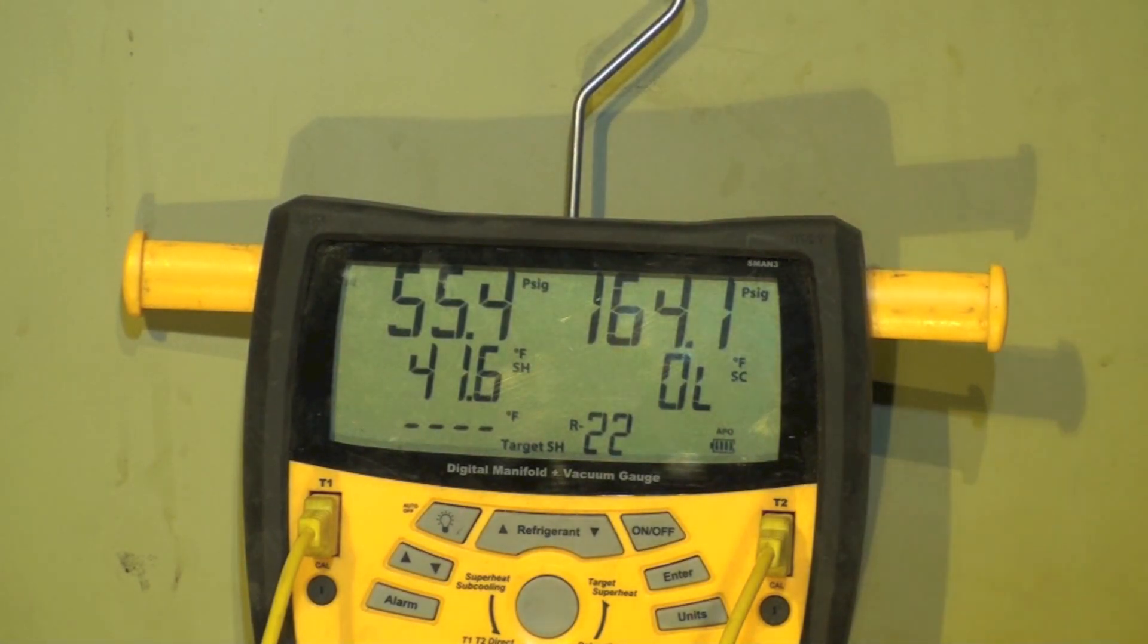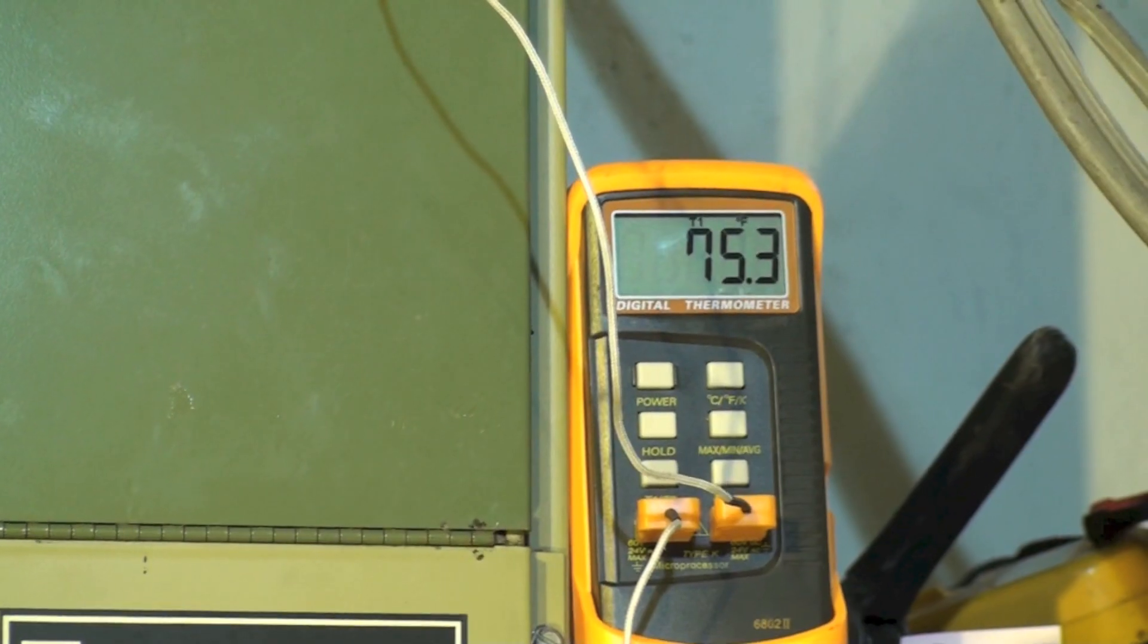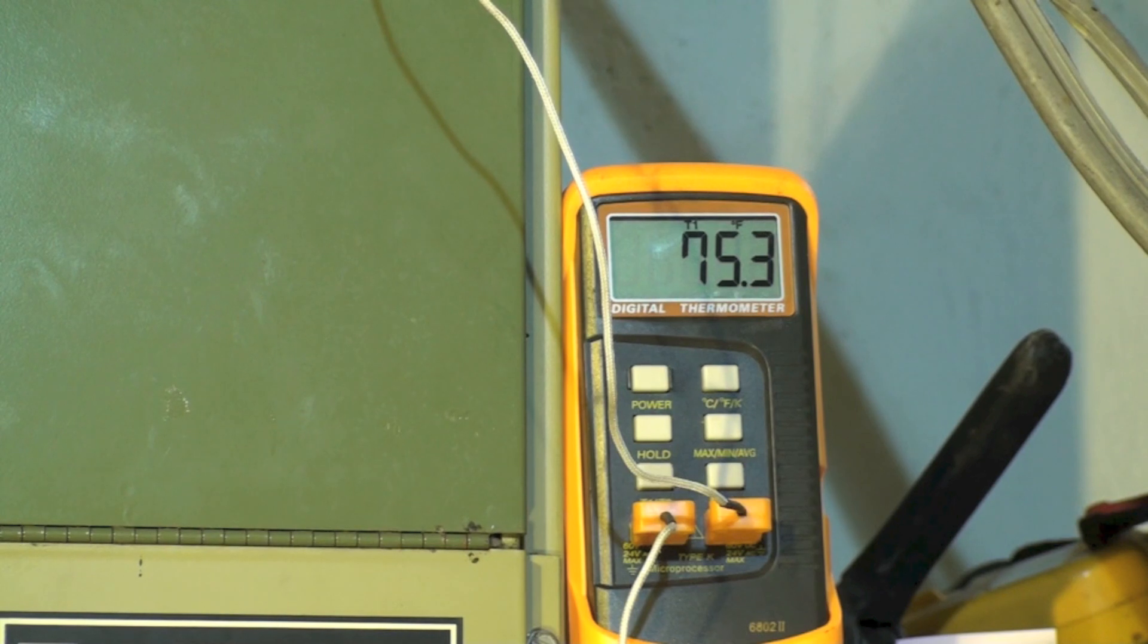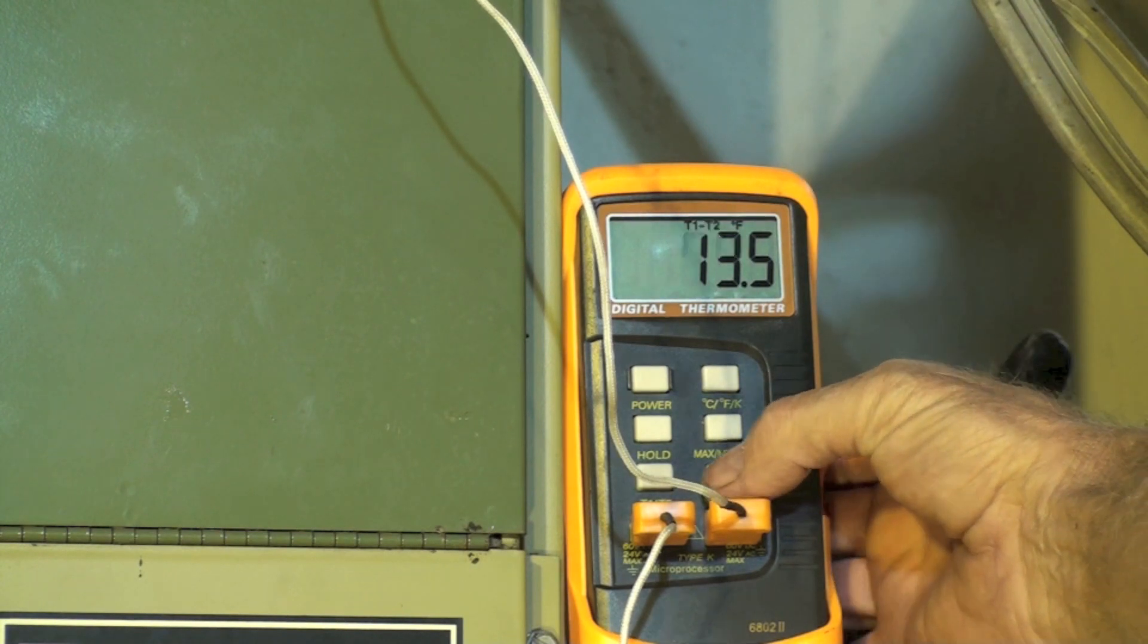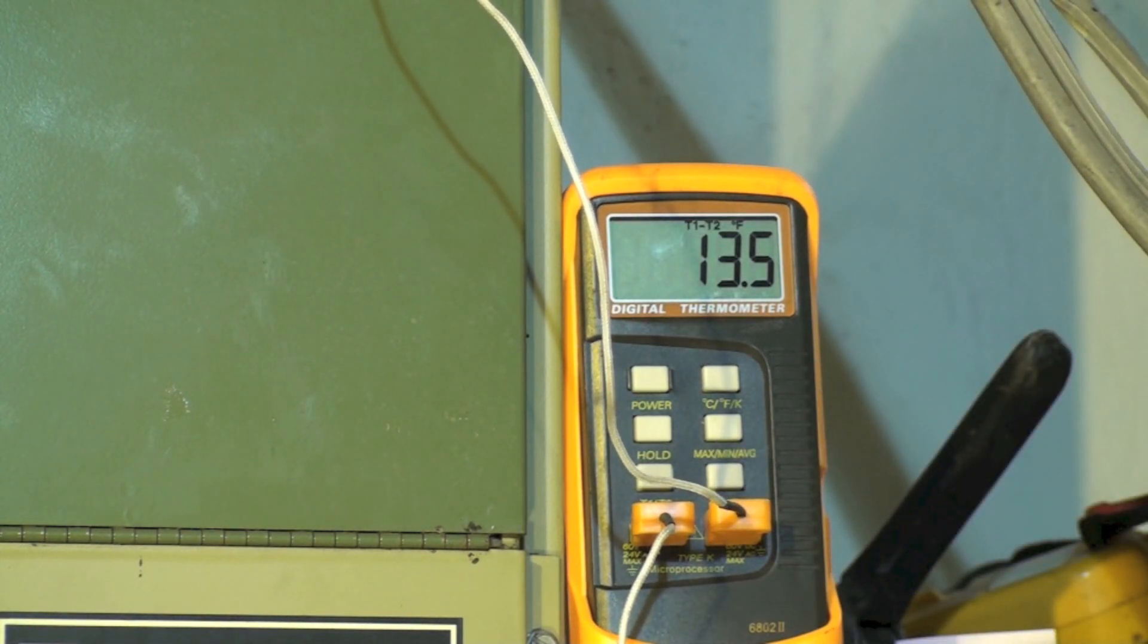Let's take a look at the temperature. Okay the temperature is 75. I'll give you a split too. Split's 13.5.